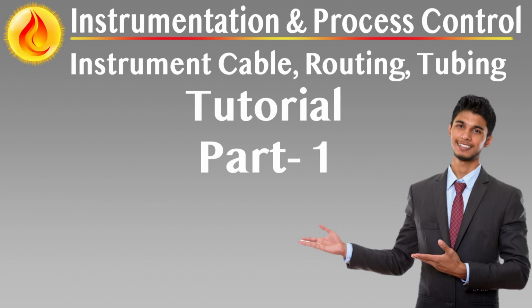Cable types for higher signal levels, classes 4 and 5. These cables carry higher energy signals, e.g. solenoids, 110 volt DC systems, and must be constructed accordingly. Conductor cross-section, minimum 2.5 millimeter squared. Cable insulation and sheathing, flame retardant, mechanically robust, and EMC compatible materials. Screening, applied as required based on proximity to instrumentation or other low voltage cables.